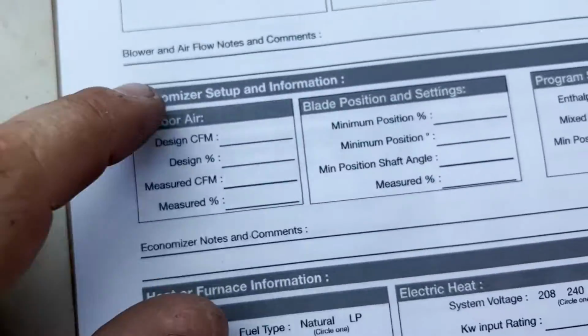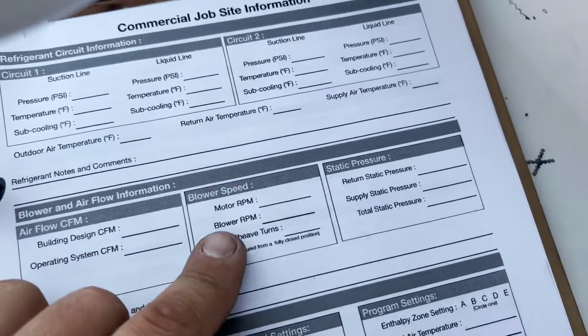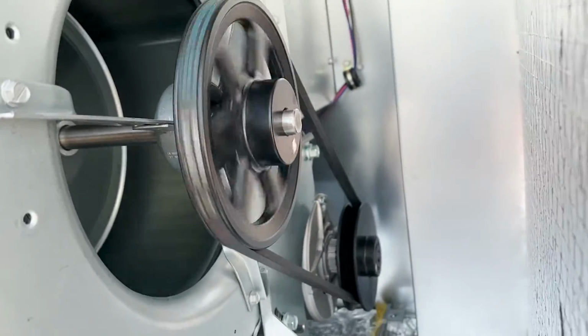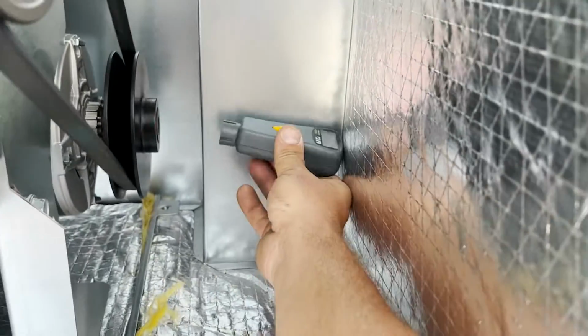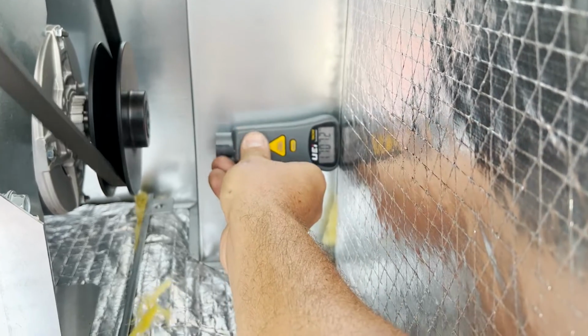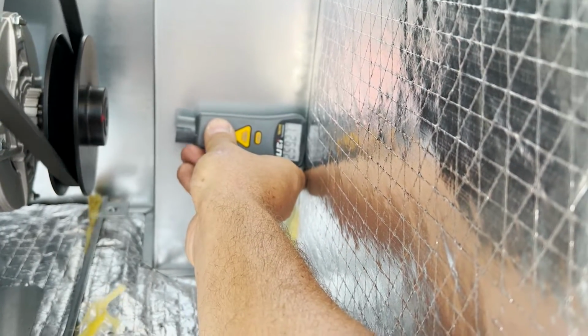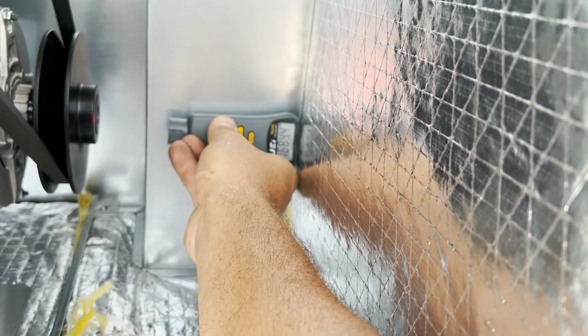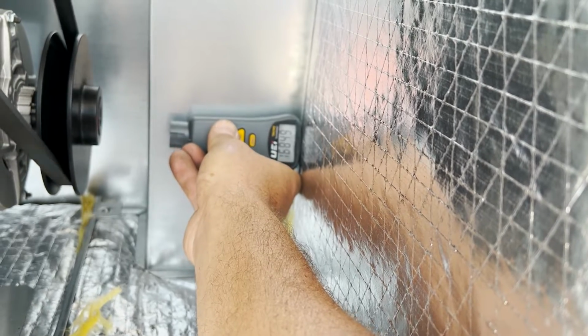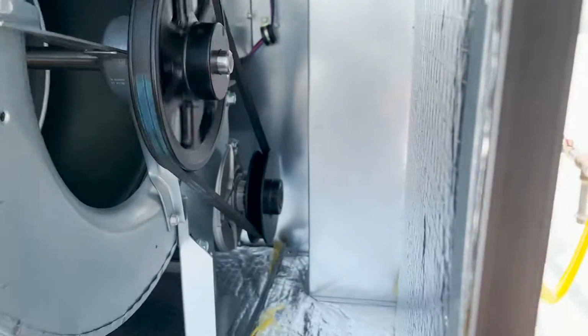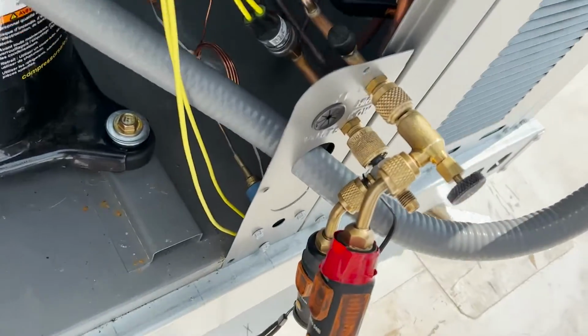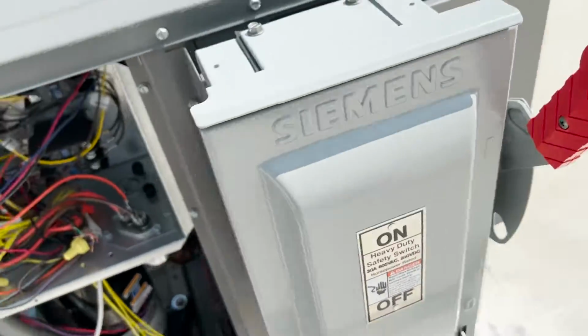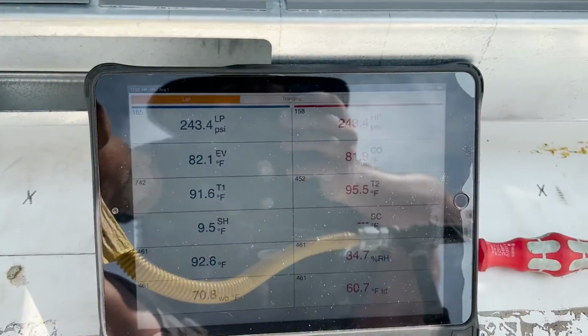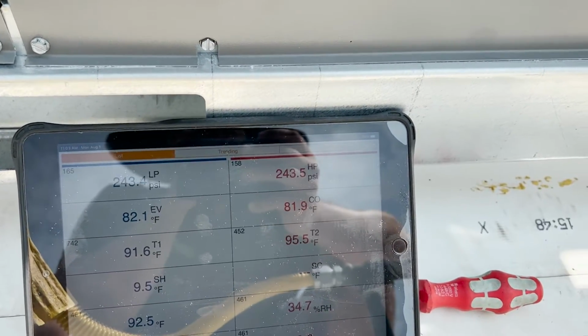All right, this particular sheet wants to see a RPM right here. So we get out the tachometer. It's 12 inches away. That on our sheet, and then we'll do it again with the motor, or that was the motor. All right, we're hooked up, we're watching our pressures. We're gonna go ahead and flip it on, and as long as these go the correct direction, we're good to go. But if those don't go the correct direction, we're gonna need to change our phase rotation.